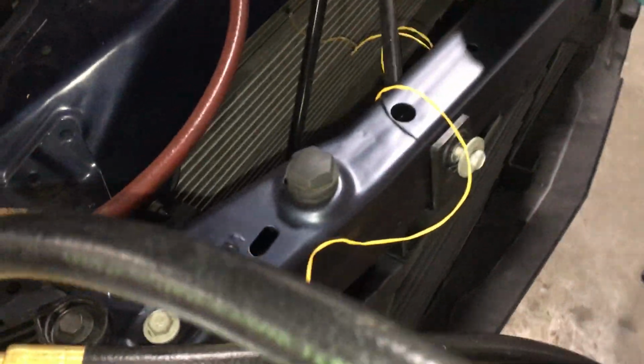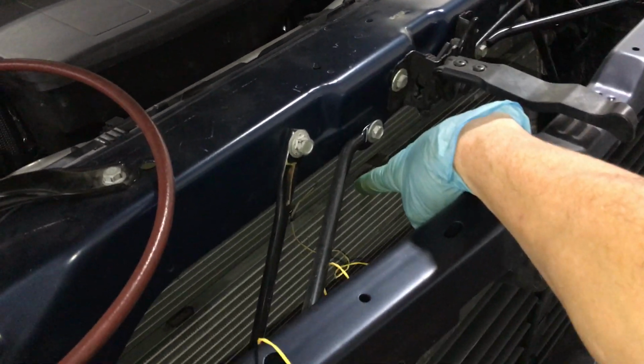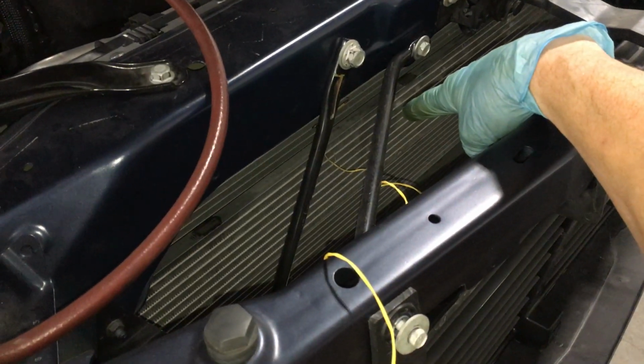Let's see. Actually, right here at this point in the shop it's actually warmer because I'm measuring from right here with the thermocouple. So I have 60 degrees air temperature being pulled across the condenser, and that's by the one that says OD dB, outdoor dry bulb temperature.